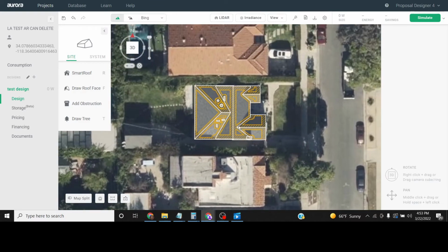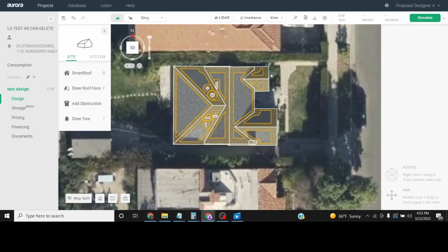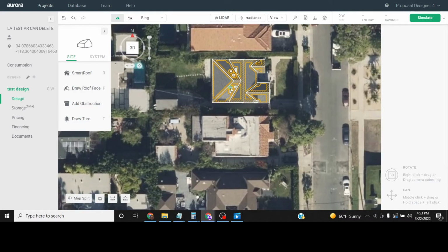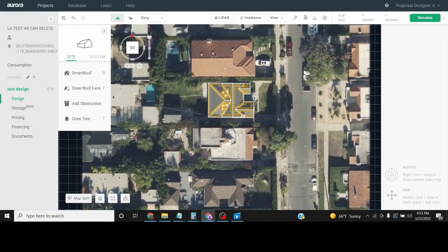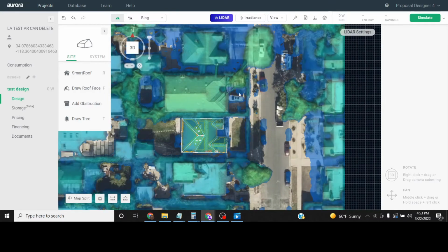The 2015 IFCs, from my understanding, are typically for firemen. If the house is on fire and for whatever reason a fireman has to get on the roof, they need pathways or walkways that are clear of panels to walk on, and that's what these are. Whether or not it seems to make a lot of sense, I'm going to keep those comments to myself.